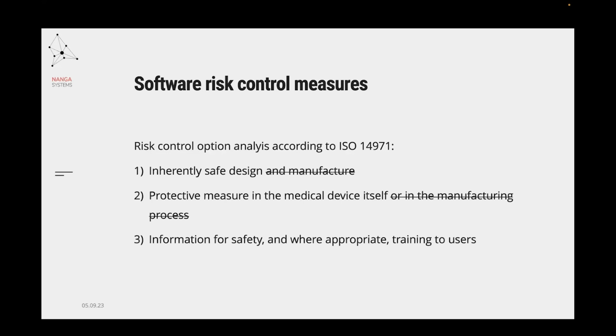For example, range checks, limitation of interfaces, limiting access to settings while treatment is happening, or access control. These are external factors, but there might be a need for internal risk control measures such as data integrity checks, calculation errors, hardware resource management. And for number three, informing and training users is basically key. And luckily in software, you do have the ability to enforce such trainings easily by granting access only after the training is completed, or you can have the user hit an OK button to acknowledge the information presented. But of course, this doesn't mean that the user actually read the information on the screen.